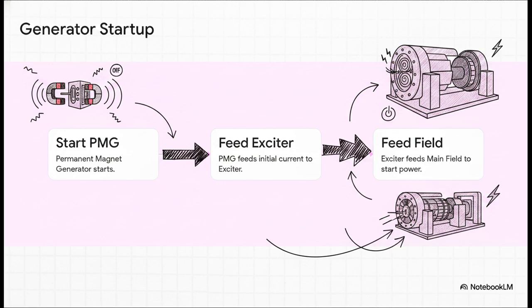Step 2, as the shaft starts spinning, the PMG creates a small initial current and feeds it right into the exciter. Step 3, the exciter takes that initial spark, ramps it way up, and supplies a massive DC current, sometimes around 5,000 amps, straight into the main generator's field.